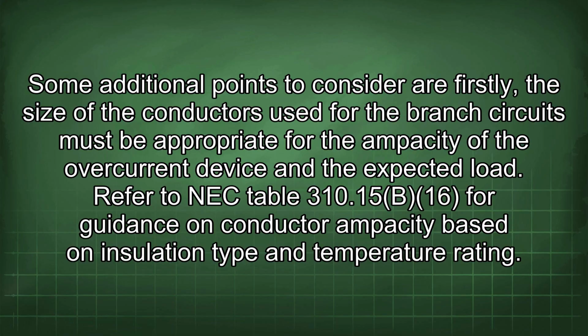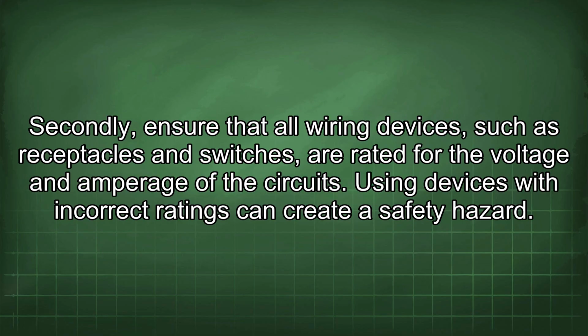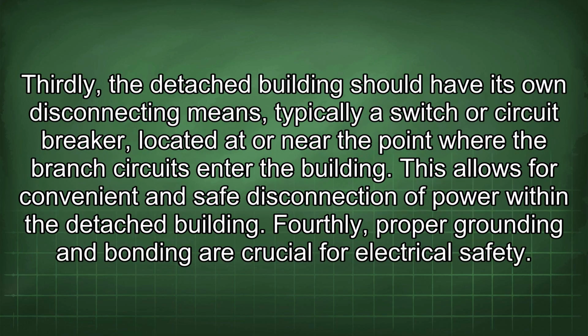Refer to NEC Table 310.15(B)(16) for guidance on conductor ampacity based on insulation type and temperature rating. Secondly, ensure that all wiring devices, such as receptacles and switches, are rated for the voltage and amperage of the circuits. Using devices with incorrect ratings can create a safety hazard. Thirdly, the detached building should have its own disconnecting means, typically a switch or circuit breaker, located at or near the point where the branch circuits enter the building. This allows for convenient and safe disconnection of power within the detached building.